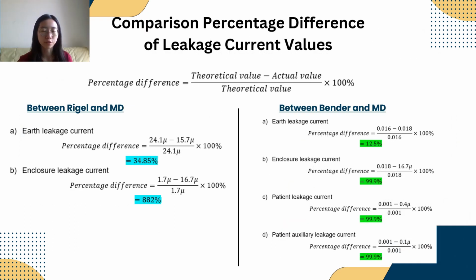Next, comparison of the percentage difference of leakage current values using different devices. We calculated the percentage difference using this formula: theoretical value minus actual value, divided by theoretical value, times 100%. Comparison between Rigel and the measuring device: earth leakage current percentage difference is 34.85% and enclosure leakage current percentage difference is 882%. Comparison between Bender and the measuring device: earth leakage current percentage difference is 12.5%, and for the enclosure LC, patient LC, and patient auxiliary LC, all of it is 99.9%.